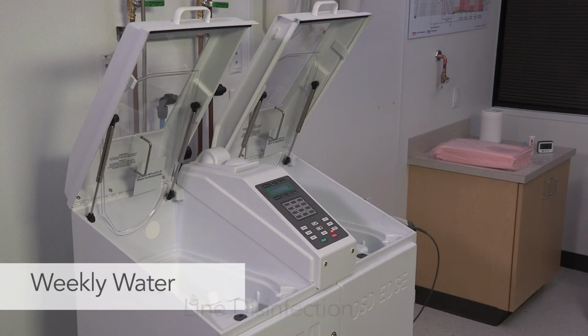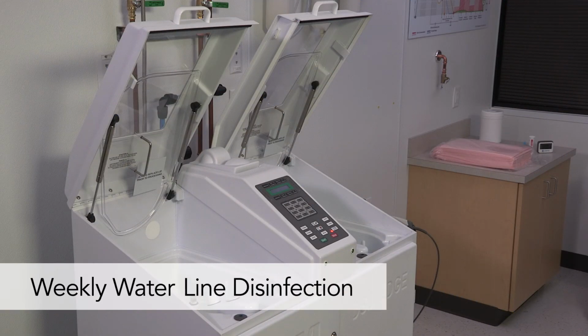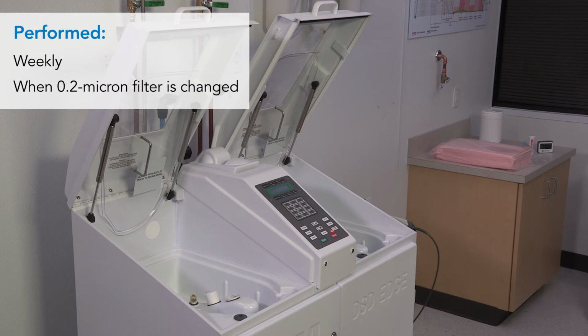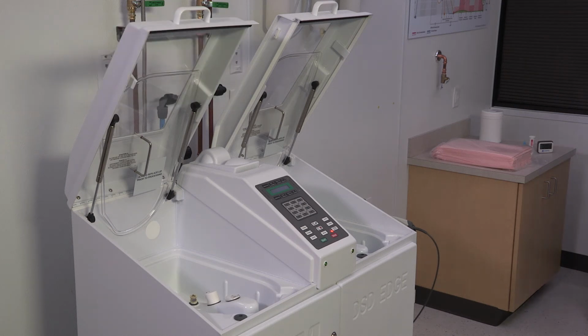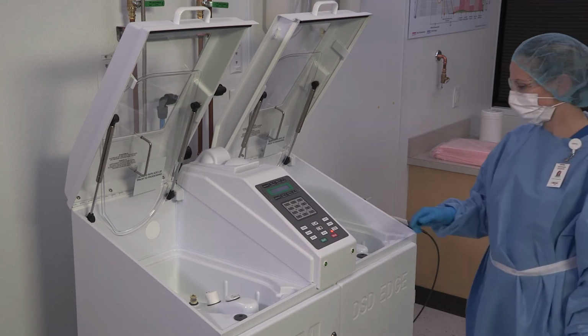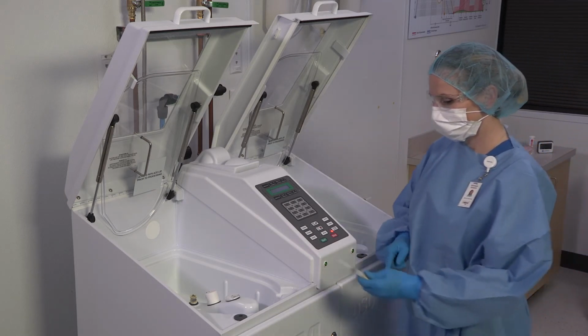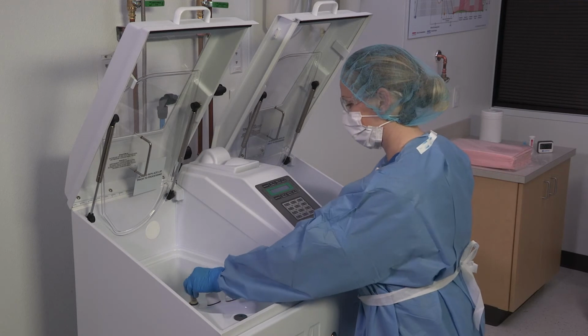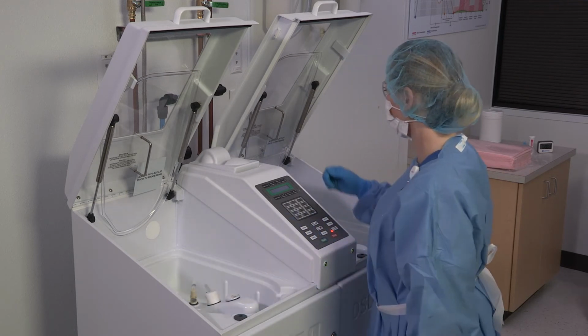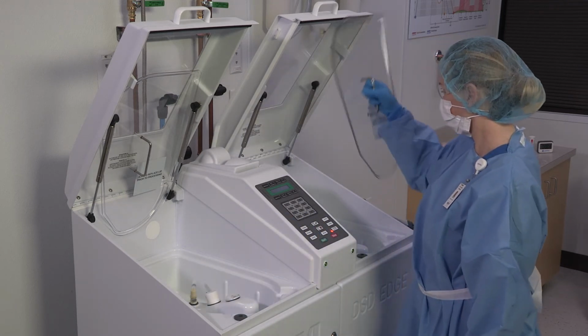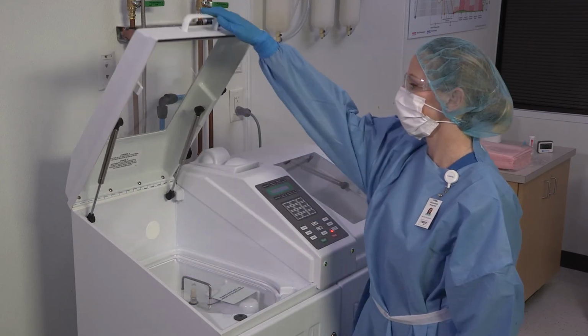We will now discuss the waterline disinfection. A waterline disinfection needs to be performed weekly and when the 0.2 micron filter is changed. To perform the waterline disinfection, the unit needs to be in an idle state. Place the basin restrictors in both the A and B basins. Position the floating lids in both basins. Close the main basin lids.